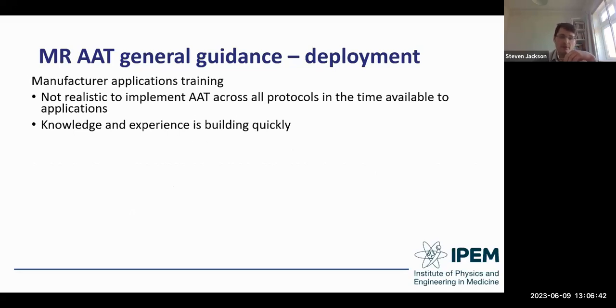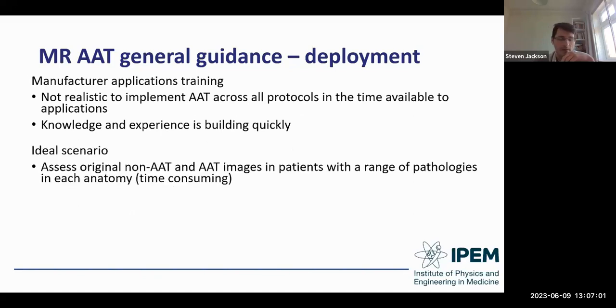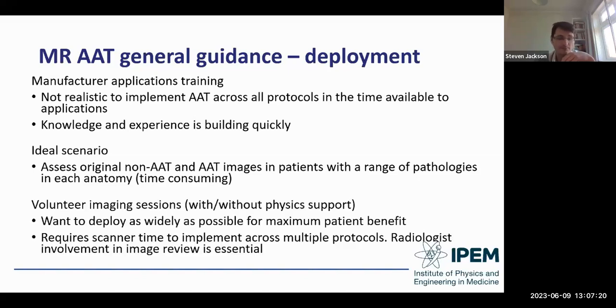In terms of deployment: as soon as the system is installed or upgraded, you have manufacturer applications training. It's not realistic to implement AAT across all protocols in the available applications time. The ideal scenario is to assess original non-AAT and AAT images in a range of patients with a range of pathologies for each anatomy. For the vast majority of sites, time isn't available to do this as thoroughly as would be best practice. In our region, we've been using dedicated volunteer imaging sessions where a list is closed for a number of hours, volunteers are scanned back-to-back with non-AAT and AAT, and a radiologist compares them before deciding whether to trial AAT in upcoming patients.